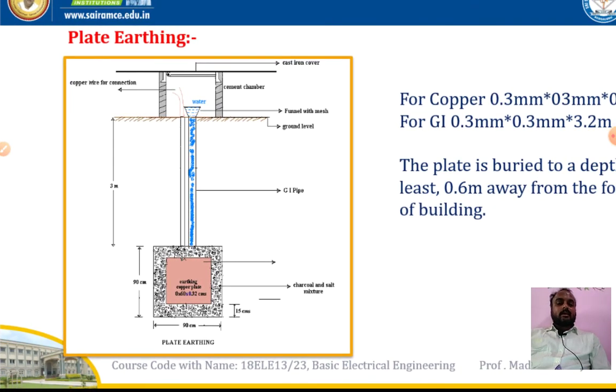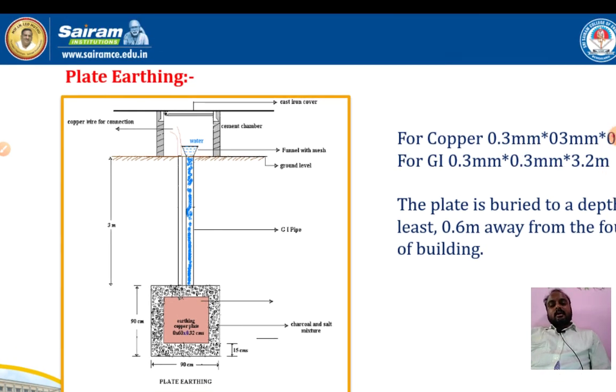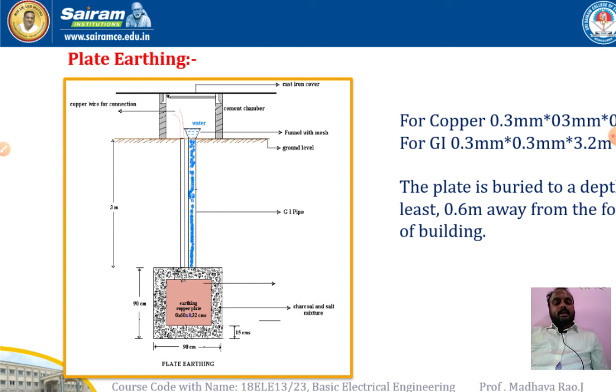This type of system is used for larger voltage rating supply systems. The pipe earthing system is normally used for buildings, homes, and apartments, etc. This type of system is used for large voltage ratings, in generating stations and transmission station systems, right? Here also, the same thing: to maintain proper conductivity we need to put layers of charcoal and salt around the earth electrode. And also in summer seasons, to maintain proper conductivity to the earth plate, we need to pump water to the funnel.